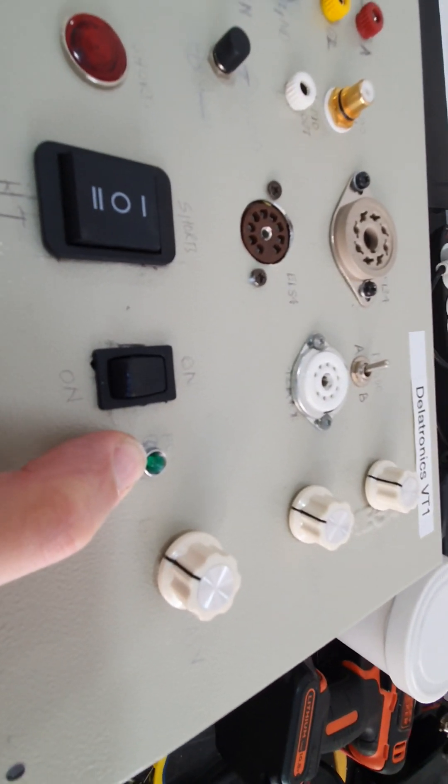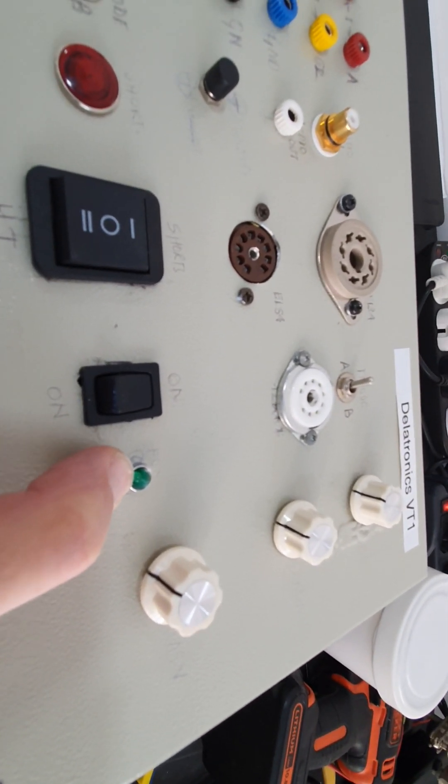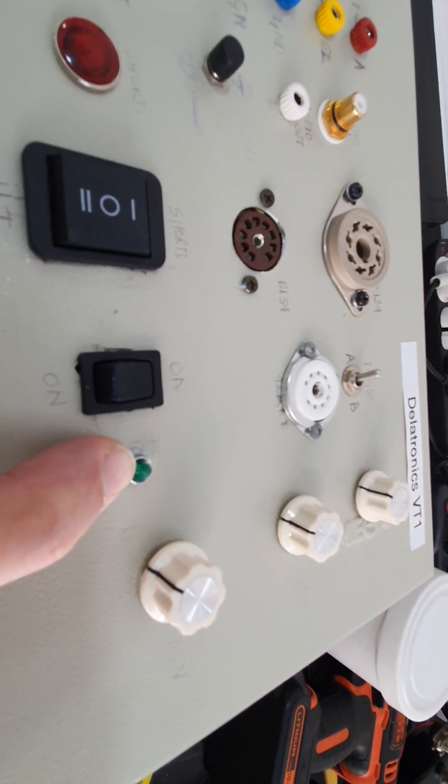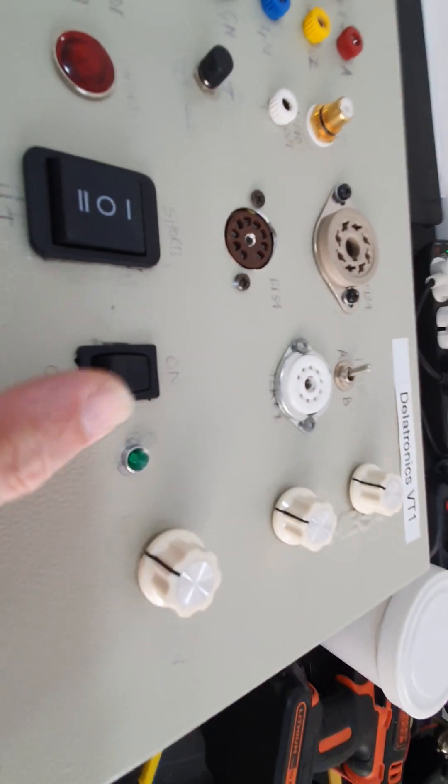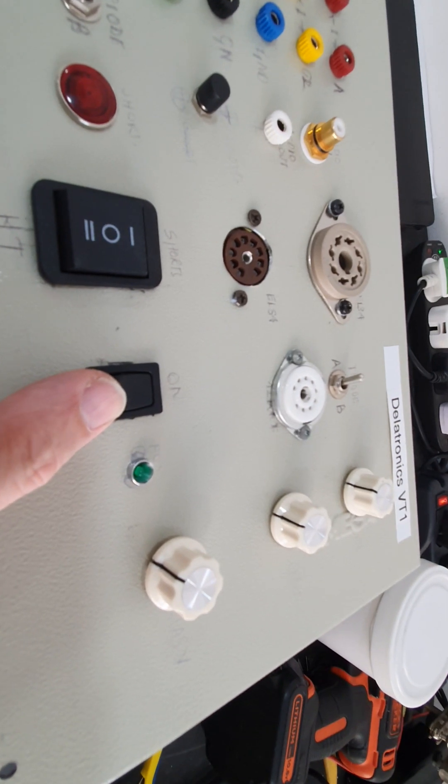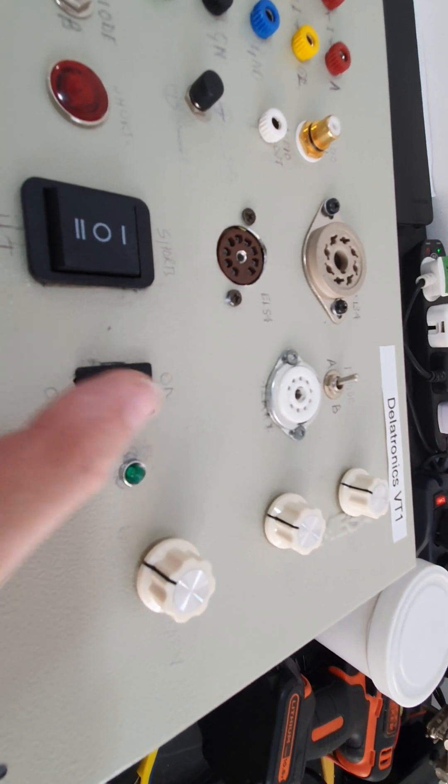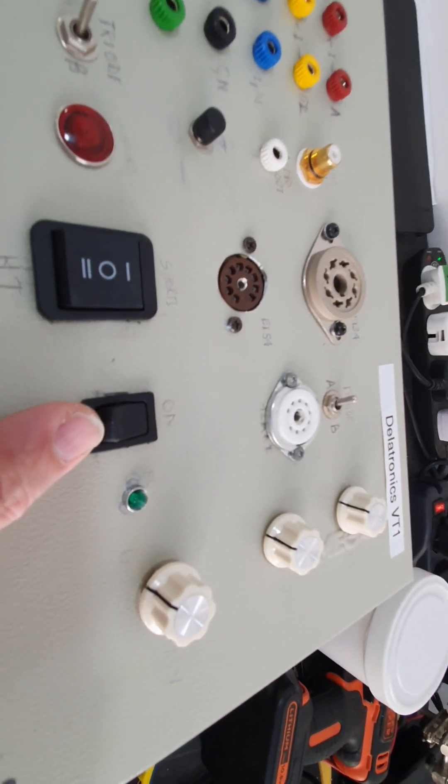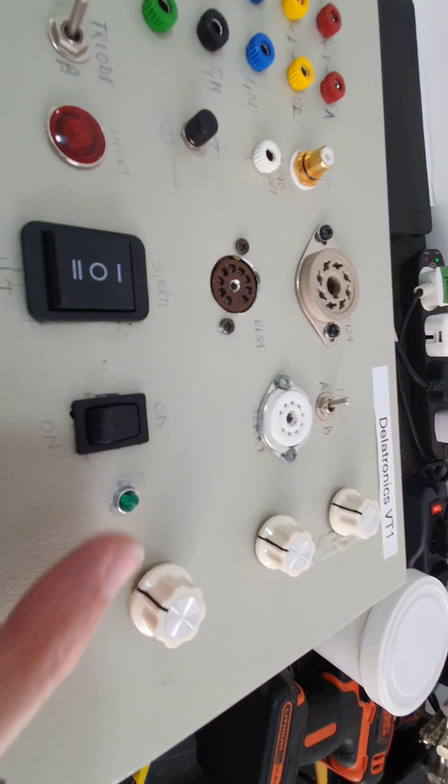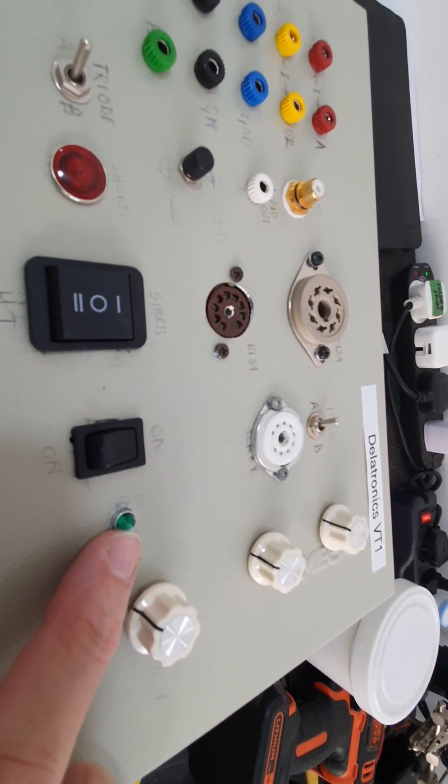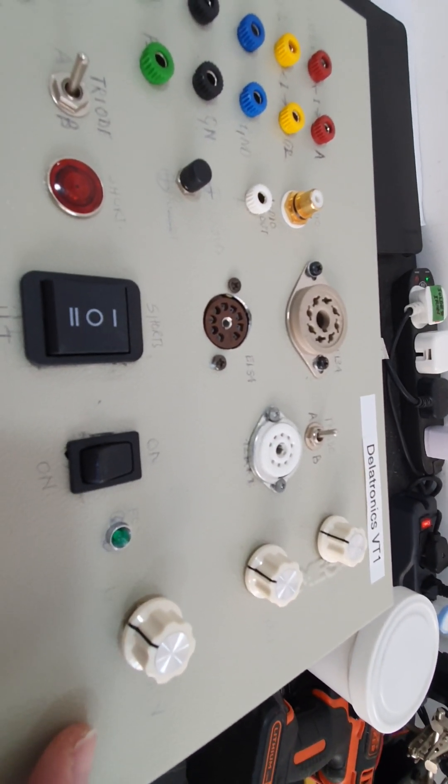This is going to be connected to the heater circuit to show that the unit's on, because I haven't got a neon in this switch. I'm going to connect to the heater circuit, and if this doesn't come on, then I know there's a problem with the heater.